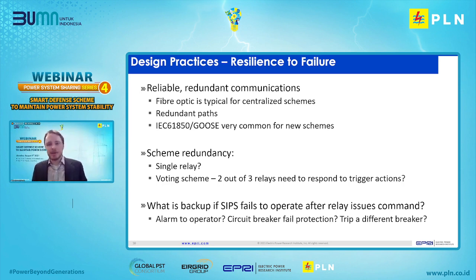So as I mentioned, it's based on the international experience. It's very important for these schemes to be resilient to failure. So typically they're almost always now implemented using fiber optic media, especially for centralized schemes with redundant paths. And 61850 and GOOSE messaging is becoming pretty much the standard for all new schemes. From a redundancy perspective, historically, these schemes were implemented using a single relay, or maybe one or two, but for high redundancy or high reliability schemes, we're seeing more companies move to voting schemes, such as those in Belgium, where we need at least 2 out of 3 or 2 out of 4 relays, all measuring the same conditions, in order to activate the scheme. And this is to prevent incorrect operation of the scheme.